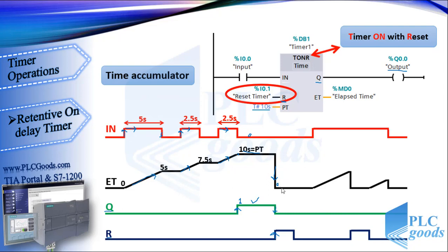Now pay attention: when both the IN and R inputs of this timer are activated simultaneously, input R takes priority over IN. So in that state, the timer will be reset.